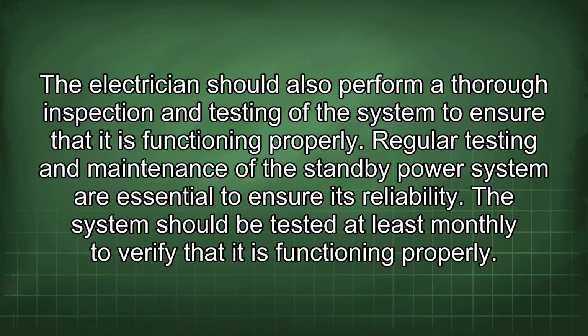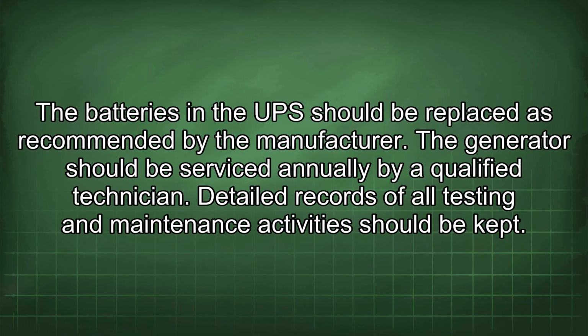Regular testing and maintenance of the standby power system are essential to ensure its reliability. The system should be tested at least monthly to verify that it is functioning properly. The batteries in the UPS should be replaced as recommended by the manufacturer. The generator should be serviced annually by a qualified technician. Detailed records of all testing and maintenance activities should be kept.